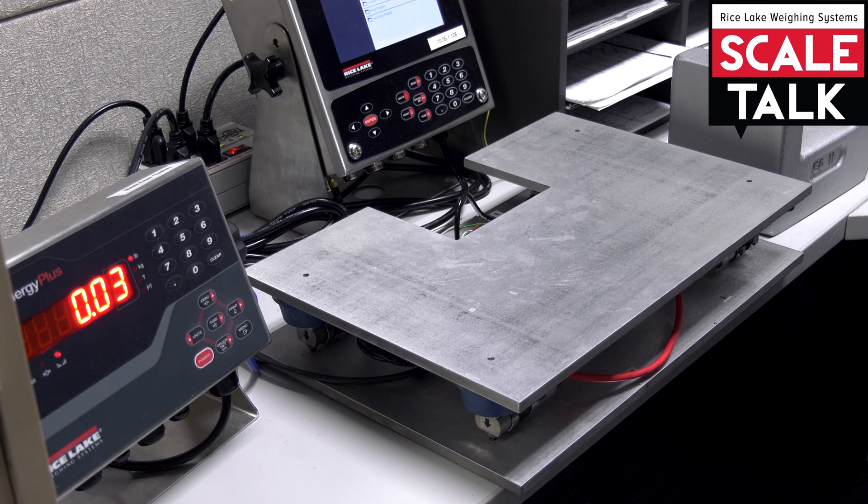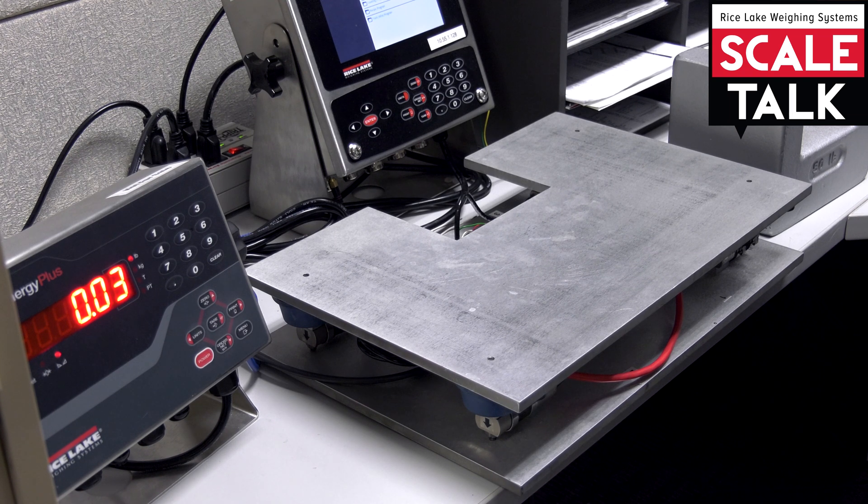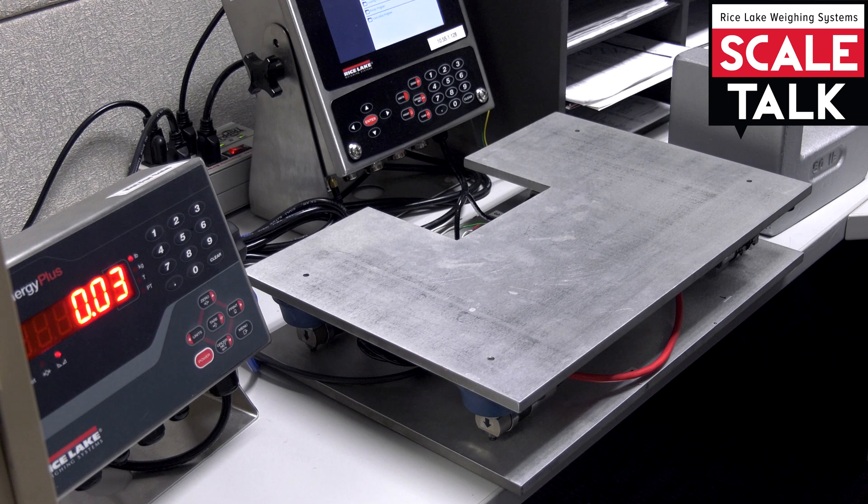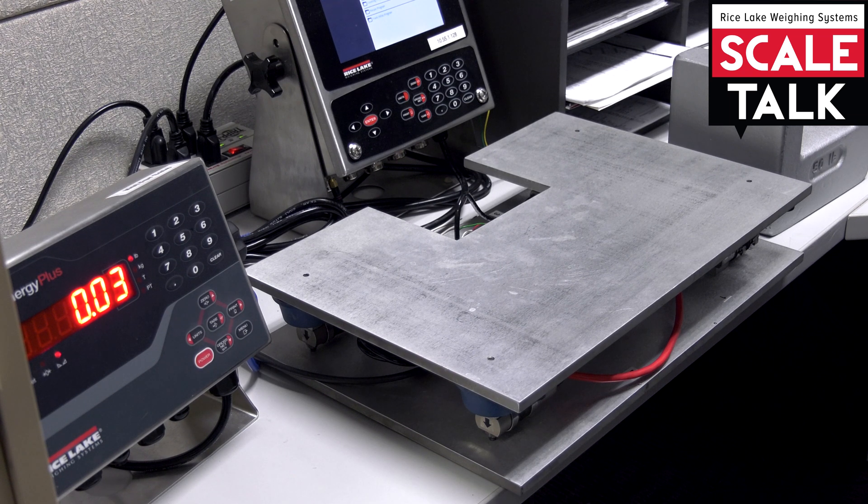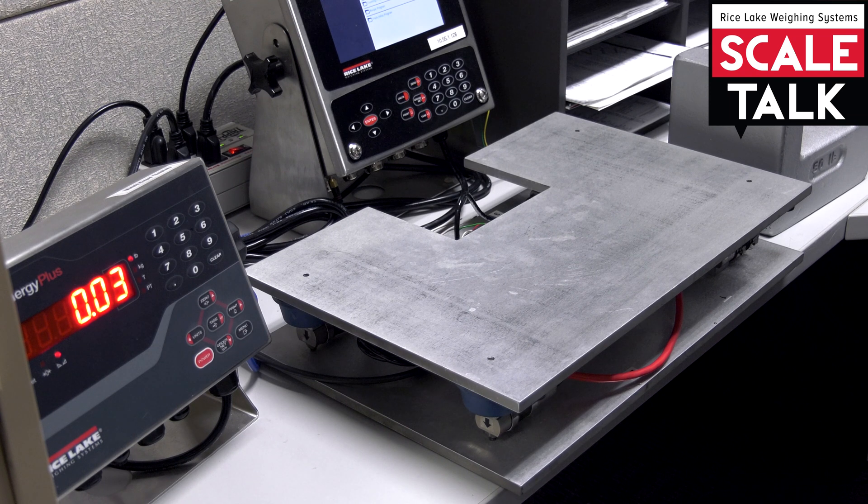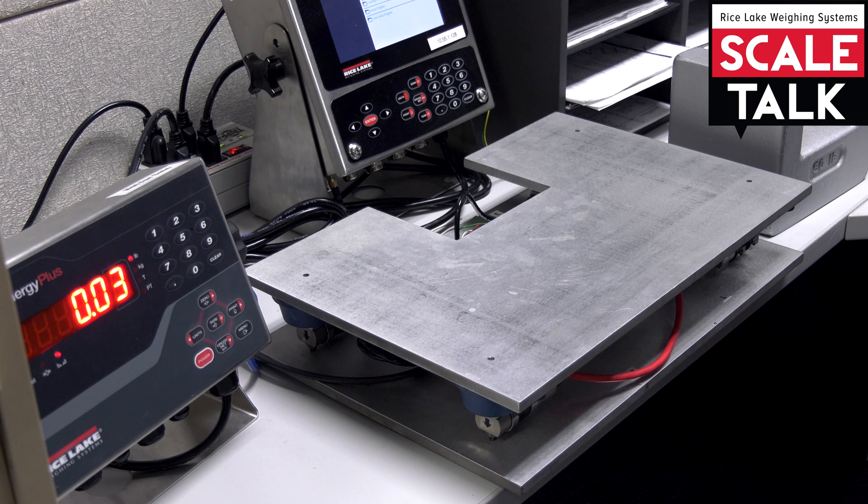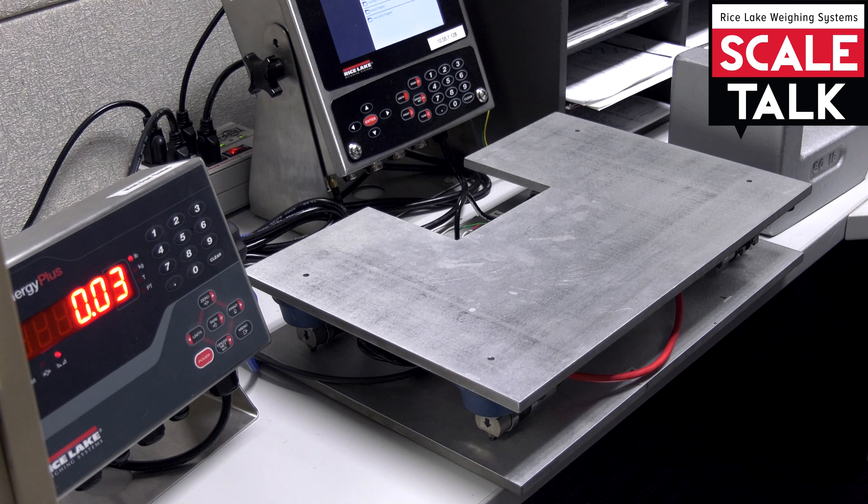And that is to use standardized test weight for calibration of your scale. Now it's important that you take a moment to reference Handbook 44 based on the capacity of your scale to determine the accepted minimum recommended amount for calibration.